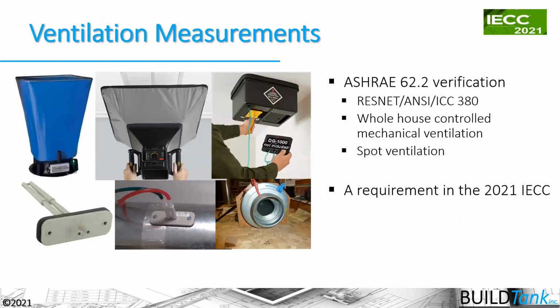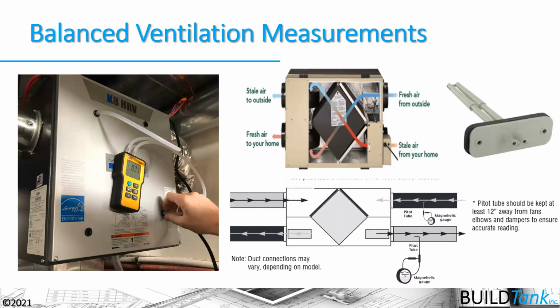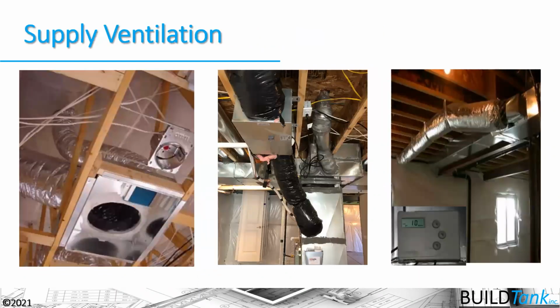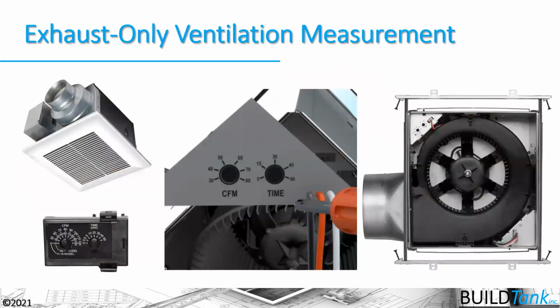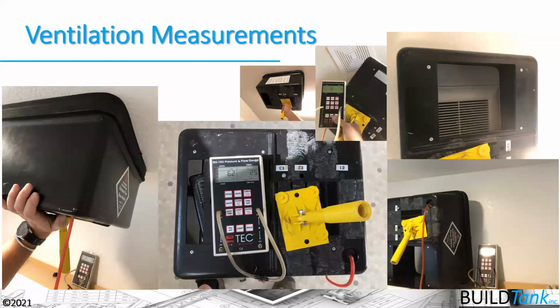These are different testing devices that are available. When you're doing balanced ventilation systems, you have to test the pressure in each of the supply and return, supply and exhaust sides of the systems. In supply side systems, you want to get that damper in there so that you can measure the flow rate. And in the exhaust side systems, there's generally a flow gauge there that you can adjust the flow of that fan, but you still need to measure it. And generally you're going to measure it using a flow box type device like this device here.